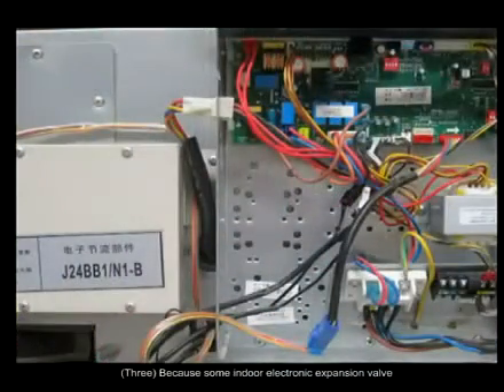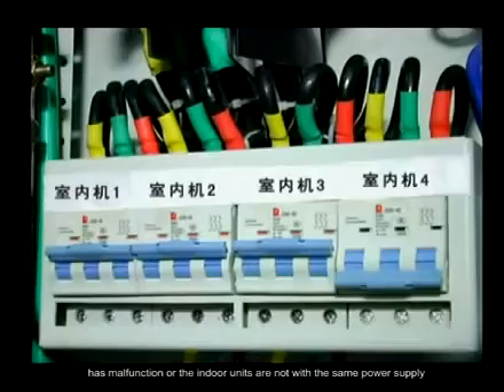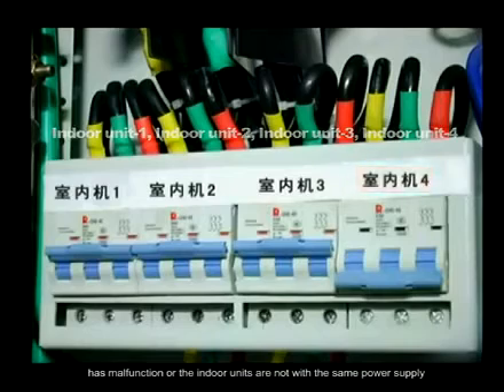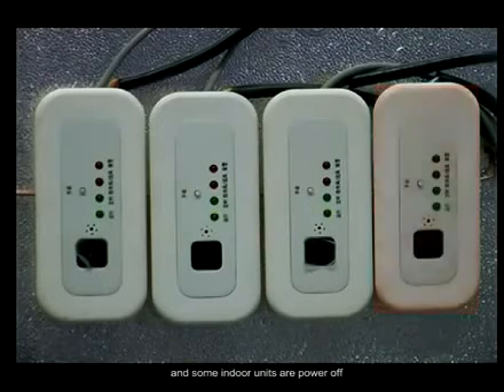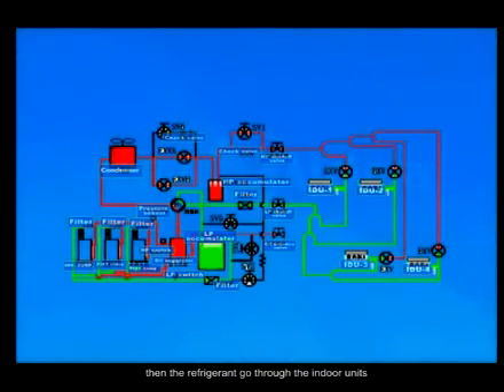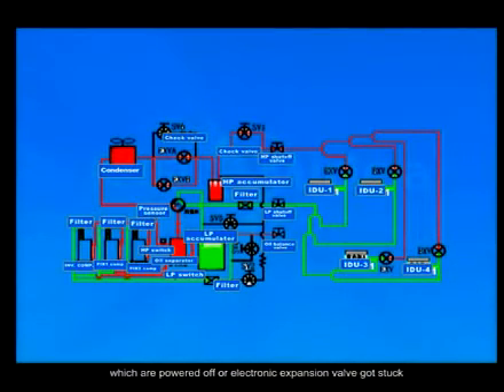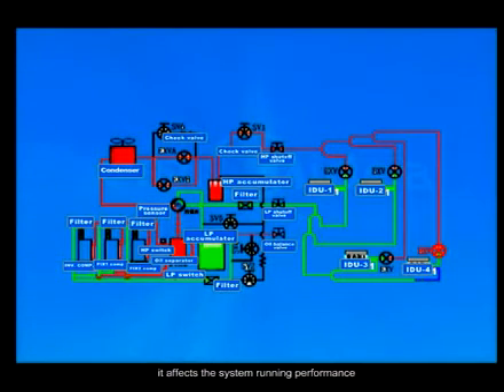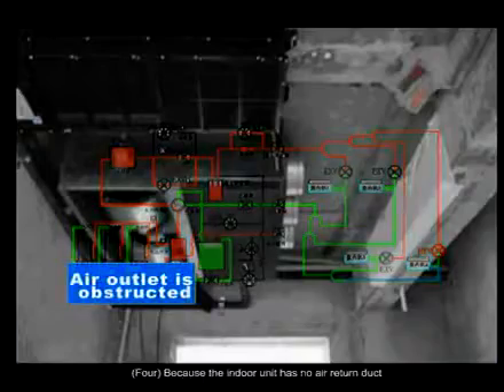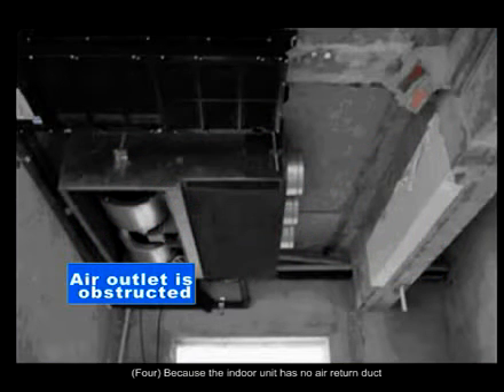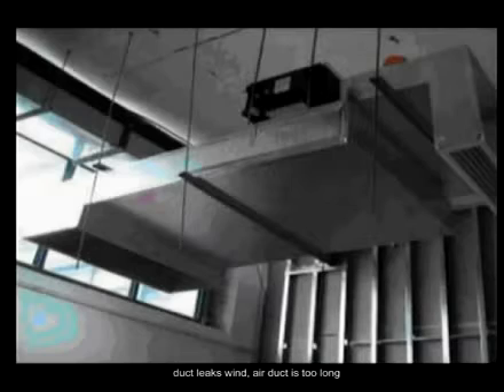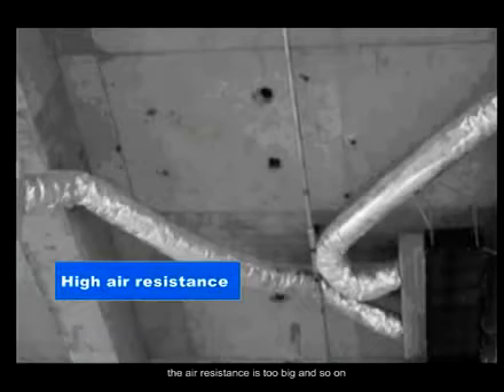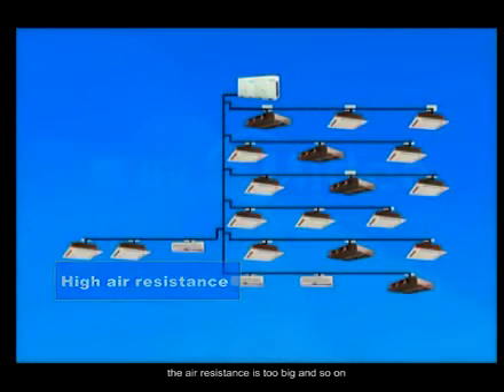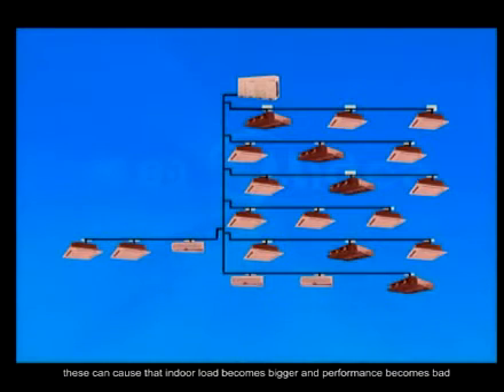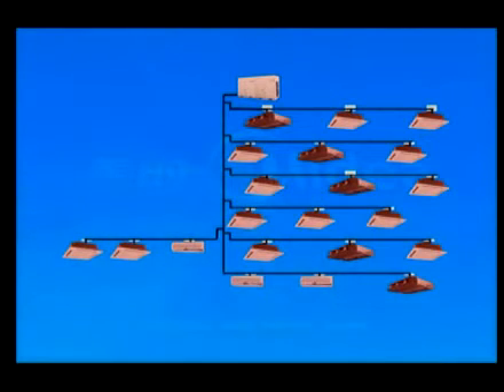3. Because some indoor electronic expansion valve has a malfunction, or the indoor units are not on the same power supply, and some indoor units are powered off, the refrigerant goes through the indoor units which are powered off, or the electronic expansion valve got stuck. It affects the system running performance. 4. Because the indoor unit has no air return, the duct leaks wind, the air duct is too long, the air resistance is too big, and so on. These can cause the indoor load to become bigger and performance to become bad.